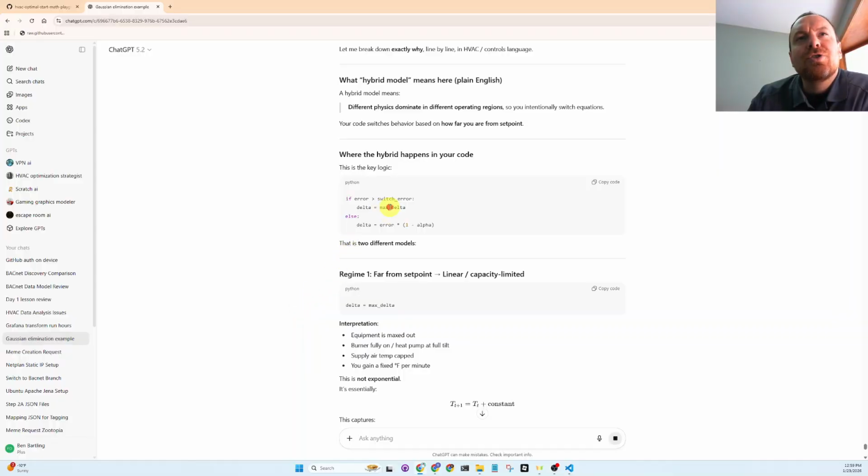I think they're just assuming some constant rate of power for a coil, in terms of BTU per hour or kW, and as soon as our delta is not very close, then it switches to some smoothing, exponential moving average type of code right there.